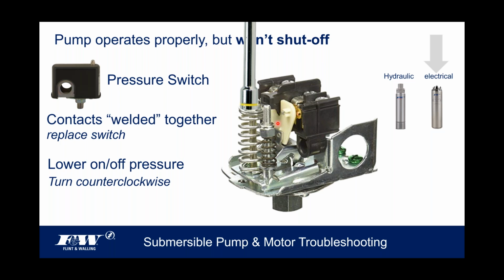As a Band-Aid, perhaps, if the pump won't shut off, I can put a hex-headed nut driver on the large spring-loaded tower where my cursor is hovering. If you take that hex nut on the top of that tower and loosen it, turning it counterclockwise, you're taking tension off of that spring. What that ultimately does is lower both your on and off pressures simultaneously. So the key here is that we're lowering the off pressure, all right? You can continue to turn that and perhaps the pump then shuts off. It just can't shut off at the 50 or 55 or 60 pounds that the switch was set at, but you may be able to get it to shut off at a lower PSI.